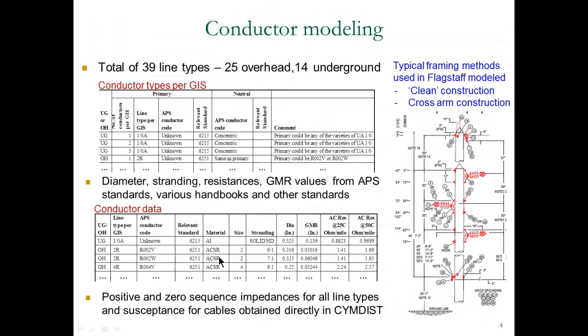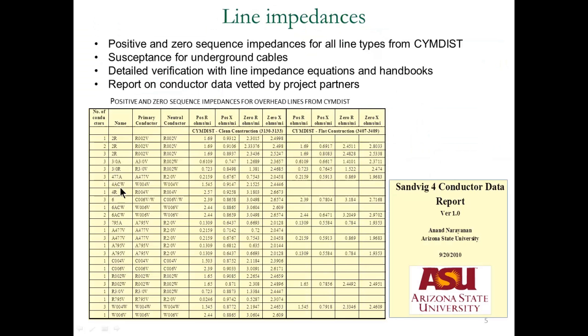So this information was used in CYMDIST, another distribution analysis software tool, to get the corresponding positive and zero sequence impedance of the various conductor types. So here is a list of the positive and zero sequence impedances for all the overhead lines as an example, and this was obtained from CYMDIST. It was also verified by a hand calculation using textbook equations, and a conductor data report was compiled for all the conductor types on the feeder, and that has been vetted by the project partners.